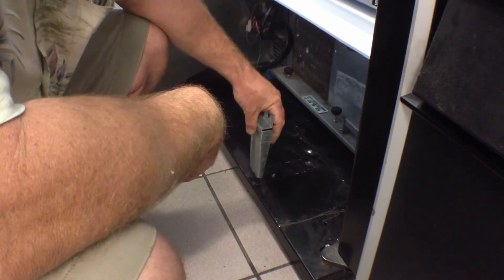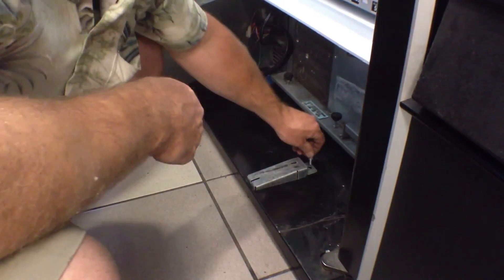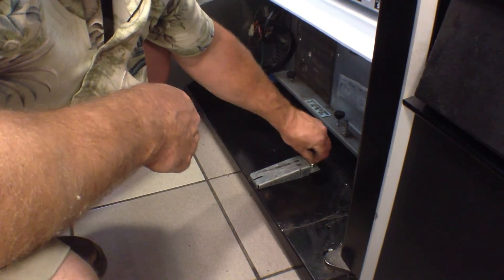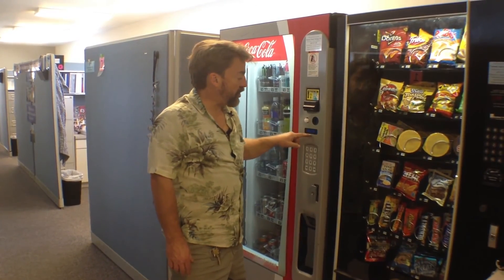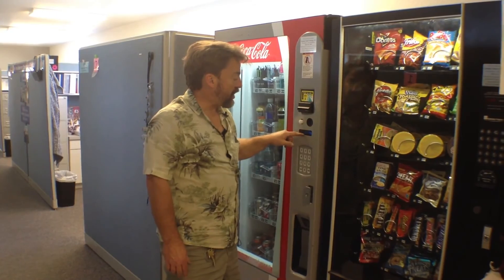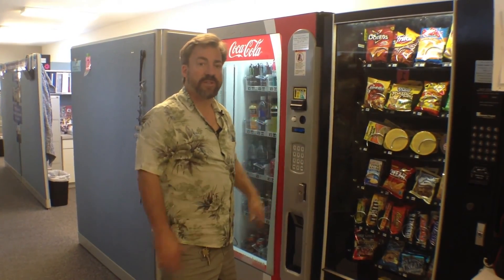One of the last things we do is put our guide back in so our door will close properly. Drop it in nose first, place it down, and then just tighten this screw. We're finished now. We've had our machine on a while and we check — we see that our temperature is dropping. It's cooling. Machine's fixed. See you next time. Thank you.